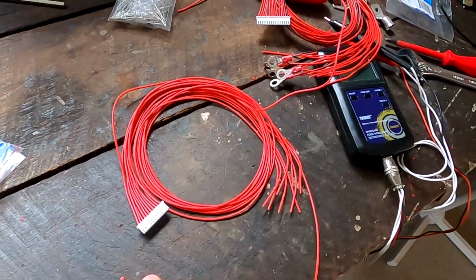You can land at 3.67 volts, which is potentially overcharging your battery. Again, I'm not too concerned about this because most people don't charge to 3.65 volts all the time. They do this probably once or twice a year to calibrate, to top balance the battery again. But even then, you could easily do this at 3.6 volts. You don't need to charge up all the way to 3.65. So only in these extreme cases, charging all the way up to 3.65 or all the way down to 2.5, and you have a certain tolerance in your measurement of the BMS, you may over discharge or overcharge your battery cells if you are not measuring accurately. So I think connect the balance leads as they come with the BMS and live your happy life.